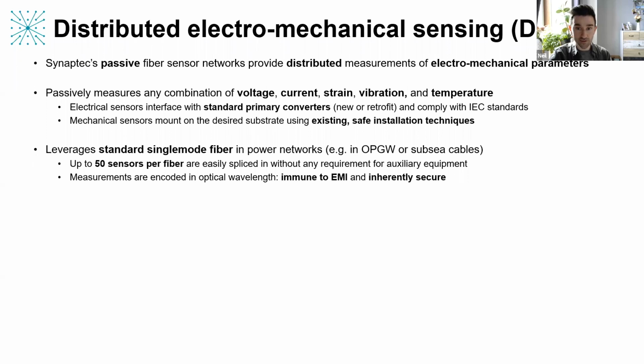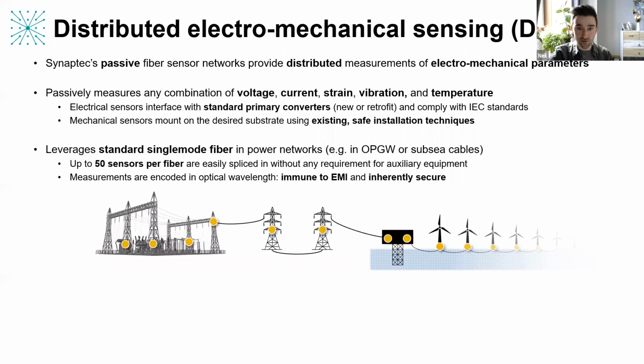The measurements from all of these sensors, regardless of the measurand, are encoded in optical wavelength, an analog optical measurement in fibre. So that means that they're immune to electromagnetic interference, which means we can distribute them over a very long distance without any degradation in quality, and they're inherently secure to hacking or other cybersecurity issues. So essentially what this means is that this technology forms a platform technology for instrumentation of power networks and can be installed really anywhere there is access to the existing fibre network.